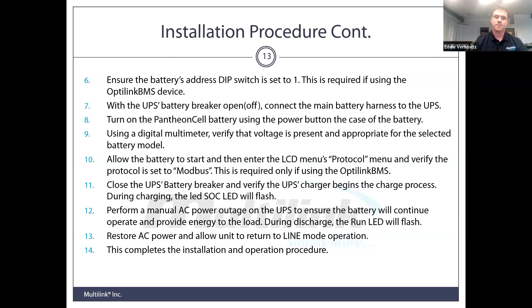After any set amount of time that may be required to perform a manual power outage, you'll restore AC power and allow the UPS to return to line mode operation. If the unit successfully returns back to line mode operation, confirm that our charge current is now flowing back into the battery. And if so, then this completes the installation and functional operation procedure of the battery.